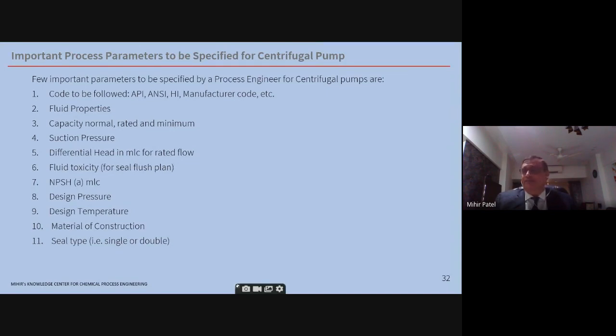Hydraulic Institute standards are followed for very large pumps, for example cooling water pumps, where you have very high flow rates and, let's say, 50 mLC, meters of liquid column, head. The Hydraulic Institute standards are followed. Manufacturer codes are followed for plastic pumps. So you may have a PP pump, polypropylene, or a UHMWPE pump, ultra high molecular weight PE, where the manufacturer codes are followed. And as you can see below, these other properties are there. All of these have to be specified by a process engineer.